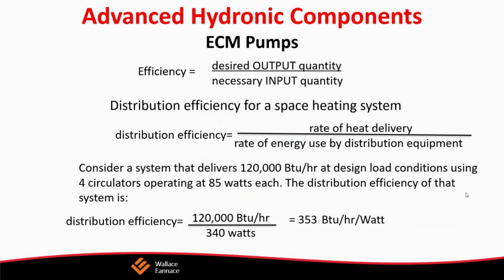So there'll be some electronics in pretty much all ECM pumps. This controller energizes the stator windings in a specific sequence to facilitate proper rotation. For proper rotation, the controller must determine the rotor position, typically via a sensor or some means of positioning. Typically, they have some sensor on there to figure out exactly where the rotor is and to keep the stator in phase with the rotor.